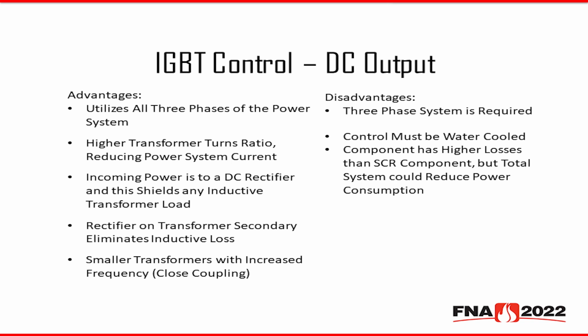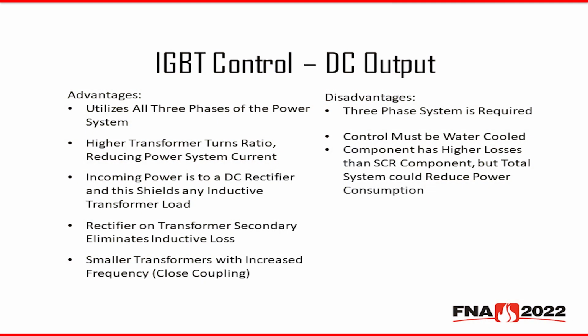Some of the downsides to an IGBT MFDC system include 3 phases upstream is required. The IGBT MFDC system is only able to produce single-phase power output, so we can't do 3-phase heating elements. Water cooling is required. And the component of the power transformations through the system sometimes have a higher total loss in some applications, and it wouldn't be useful in those applications.